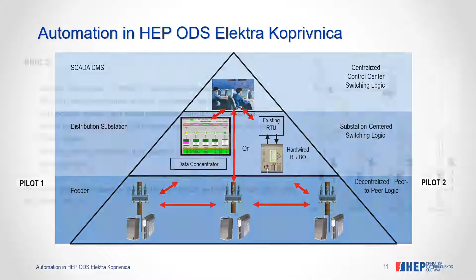You see there above is the control center. That's a distribution substation in the middle, and down are the 3 reclosers. They only communicate with the control center vertically. And then we came to pilot 2. It's a decentralized system, so the reclosers communicate with each other horizontally, with their own logic, and also with the control system in the center.